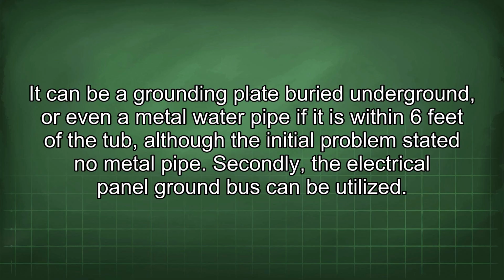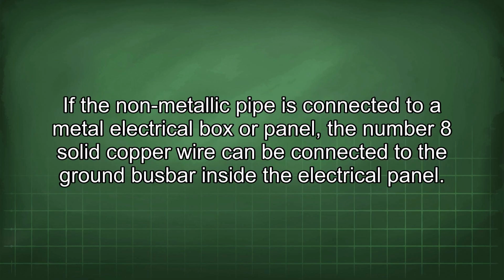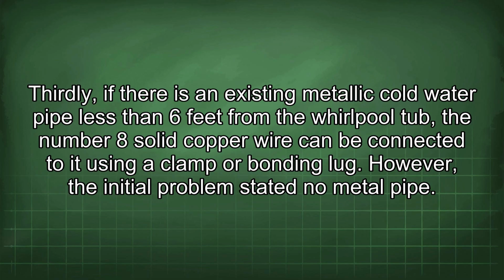Secondly, the electrical panel ground bus can be utilized. If the non-metallic pipe is connected to a metal electrical box or panel, the number 8 solid copper wire can be connected to the ground bus bar inside the electrical panel. Thirdly, if there is an existing metallic cold water pipe less than 6 feet from the Whirlpool tub, the number 8 solid copper wire can be connected to it using a clamp or bonding lug. However, the initial problem stated no metal pipe.